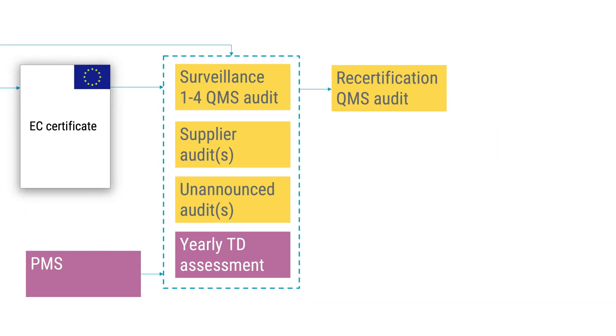Within 12 months of the certification date, the notified body needs to perform the first annual surveillance audit, and once again there should be a TD assessment performed in conjunction with this audit. The requirement is that technical documentation shall be sampled and assessed yearly until the full range of the manufacturer's devices has been covered. According to MDCG 2019-13, the depth of the TD assessment shall actually be the same for class 2a, 2b, and class 3.